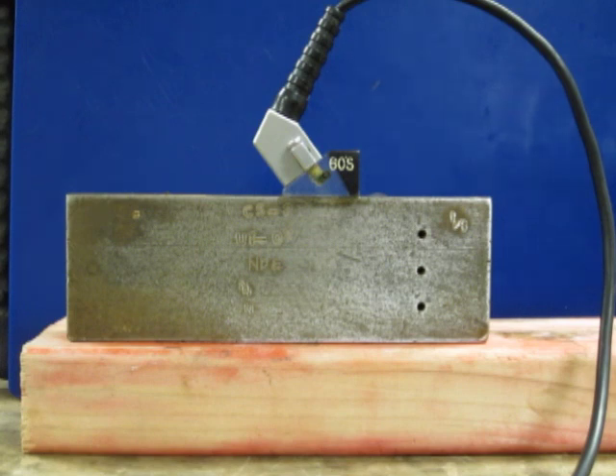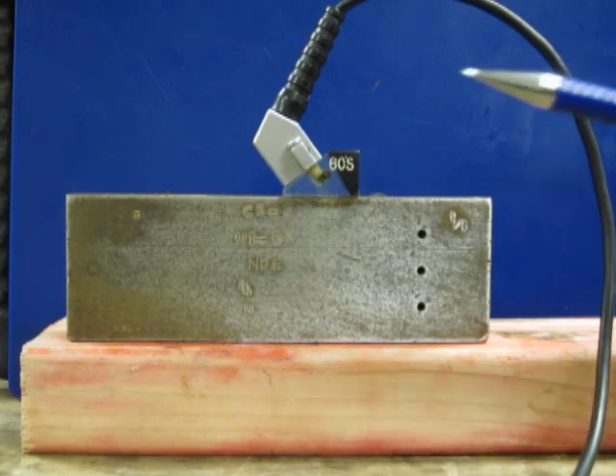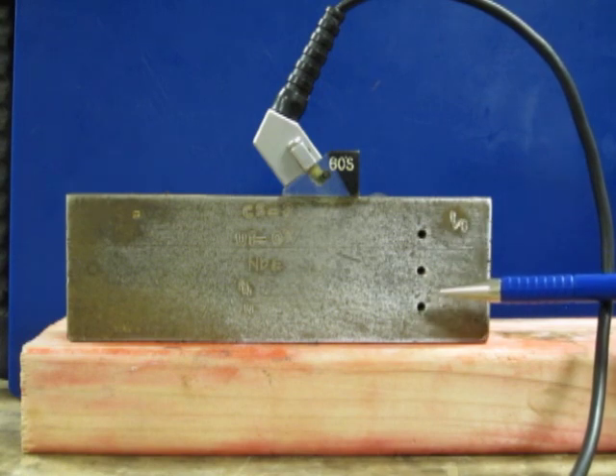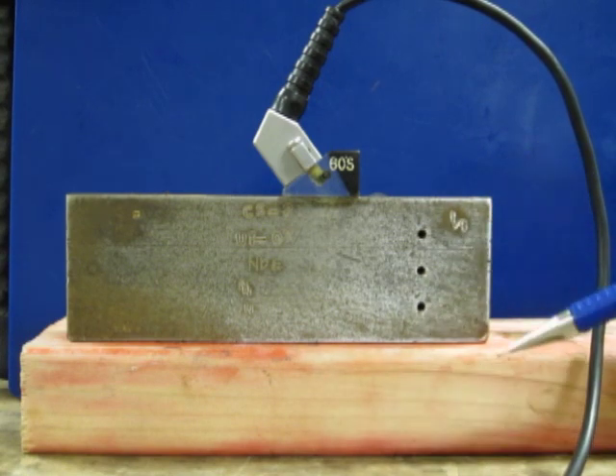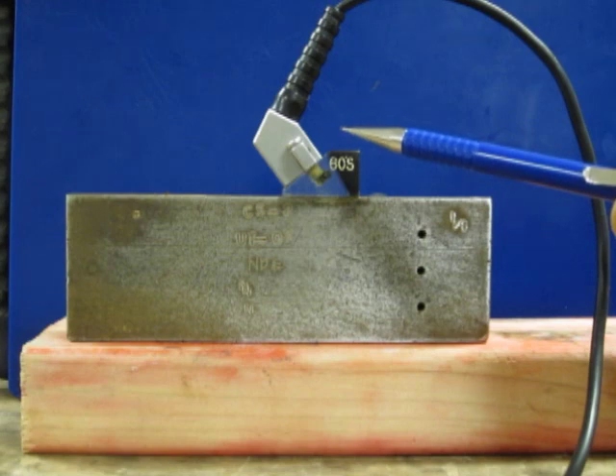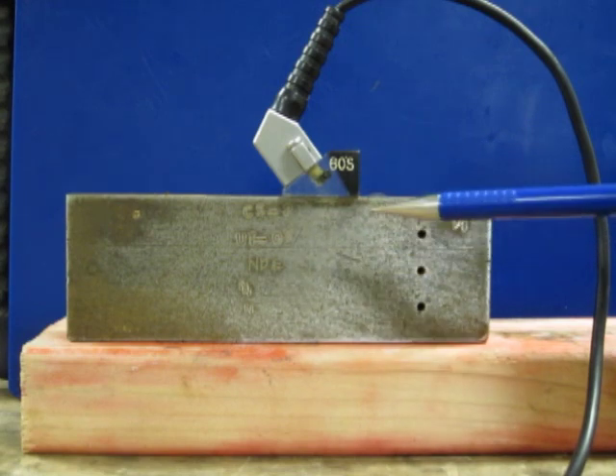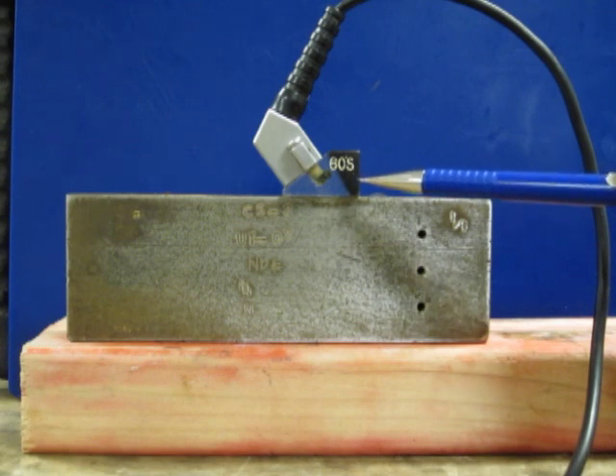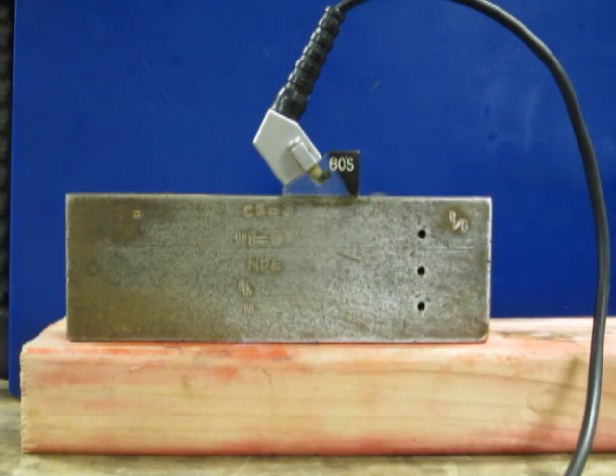Let me give you a quick demonstration of the phased array concept. Here we have a two inch block with three side drill holes at half inch, one inch, and one and a half inches. I have a five megahertz phased array probe here with a nominal refracted angle of 60, but I will be sweeping the beam from 30 degrees to 75 degrees.